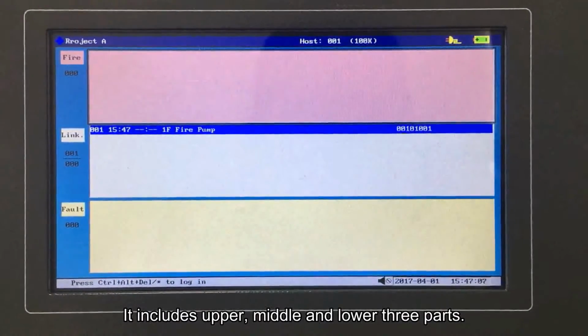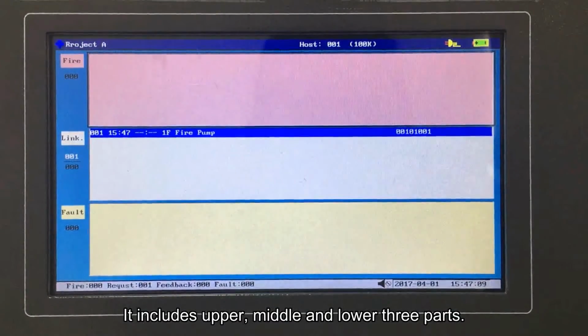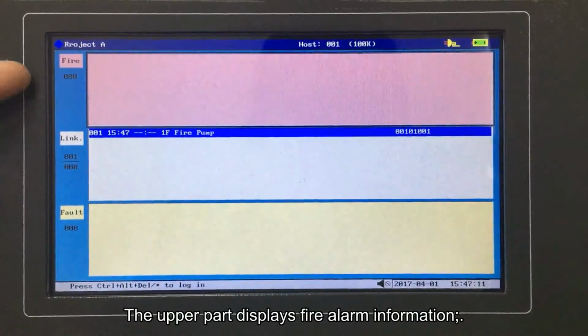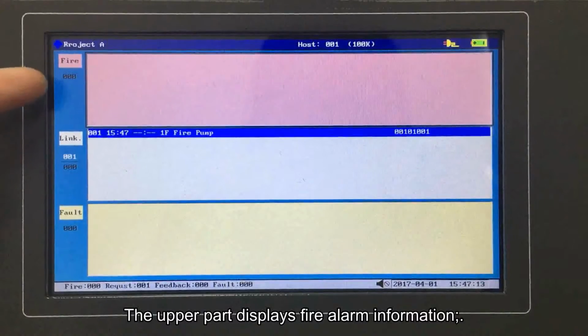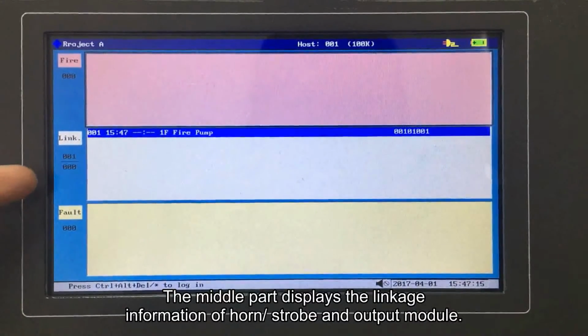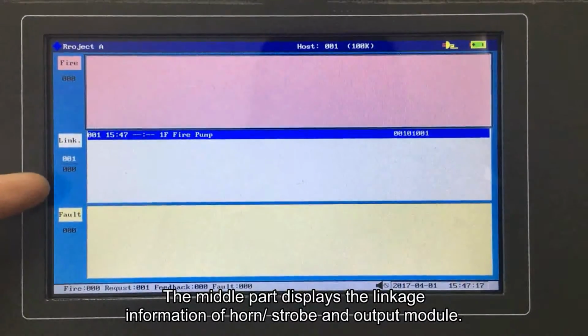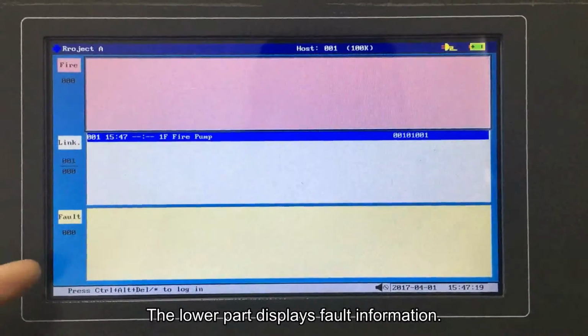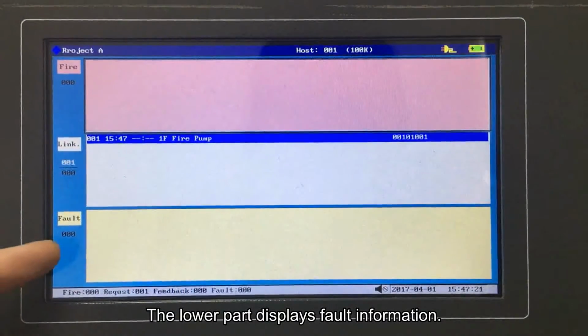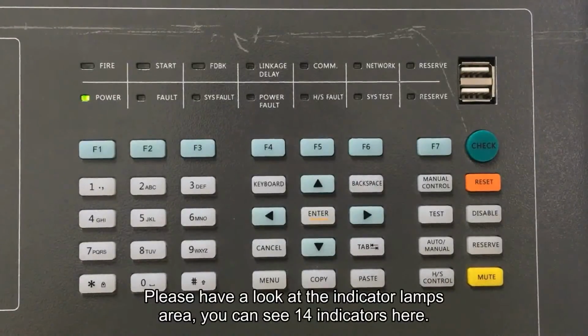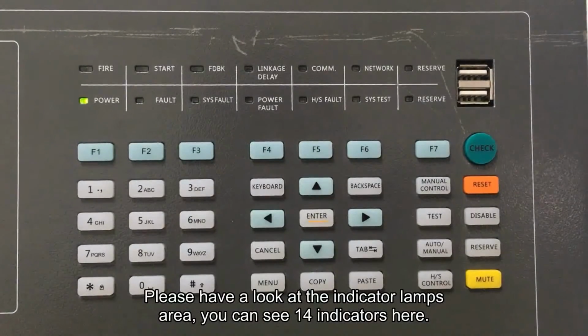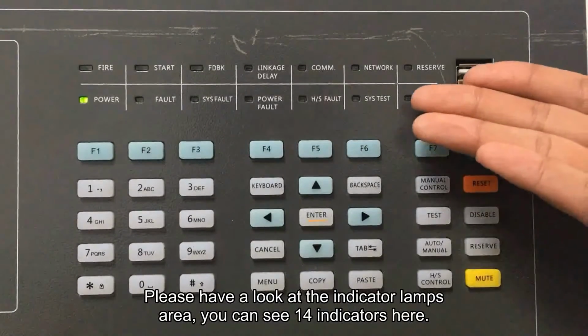It includes upper, middle, and lower 3 parts. The upper part displays fire alarm information. The middle part displays the linkage information of horn strobe and output module. The lower part displays fault information. Please have a look at the indicator lamps area. You can see 14 indicators here.